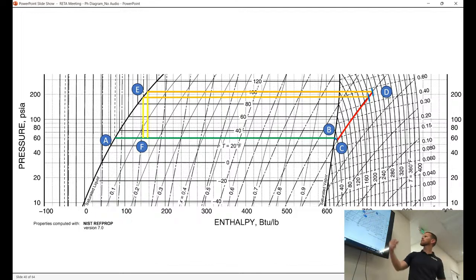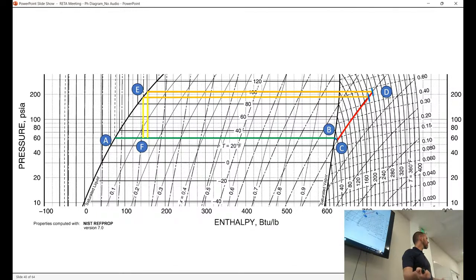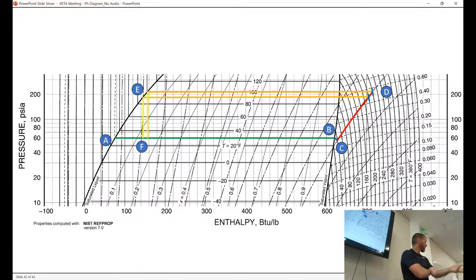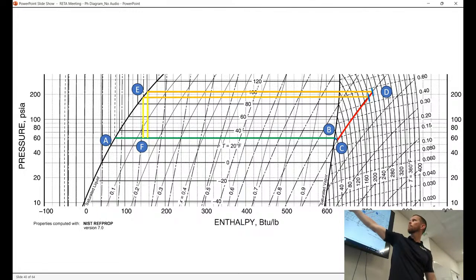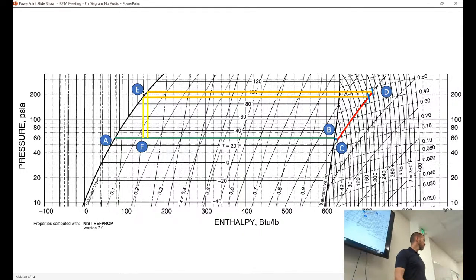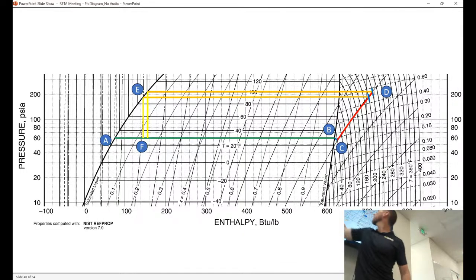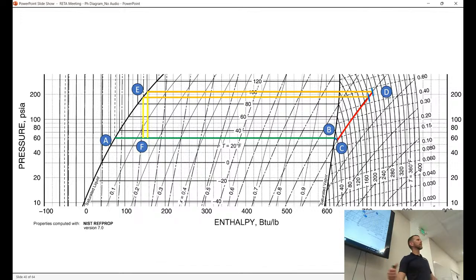What happens when we increase condensing pressure? It needs to go up further. That's going from 200 to 220 degrees discharge temperature — maybe not a big deal right now, but day in, day out, week in, week out, year in, year out, it's going to have its effects. And look what it did at point F — it moved our point F because now we hit the saturated liquid line at a point further to the right. So we have a little bit more flash gas and therefore less refrigeration effect. Is this a net positive or a net negative? Negative. That's no good.